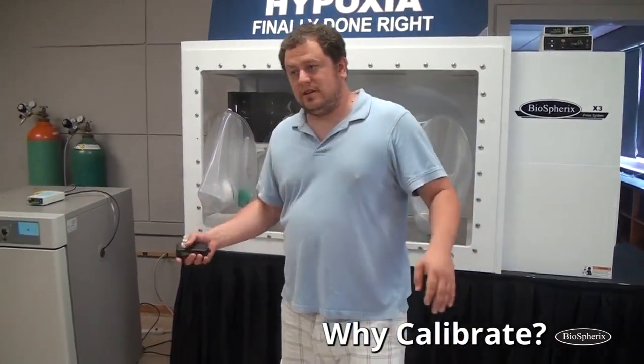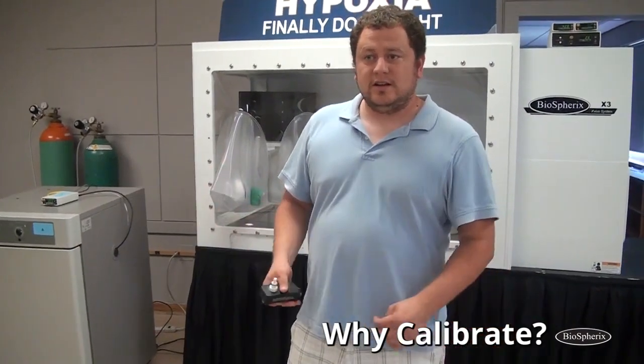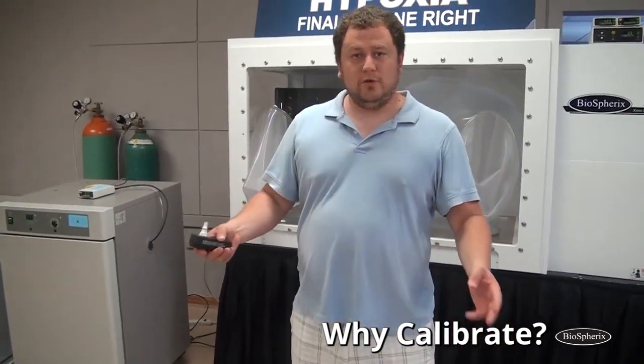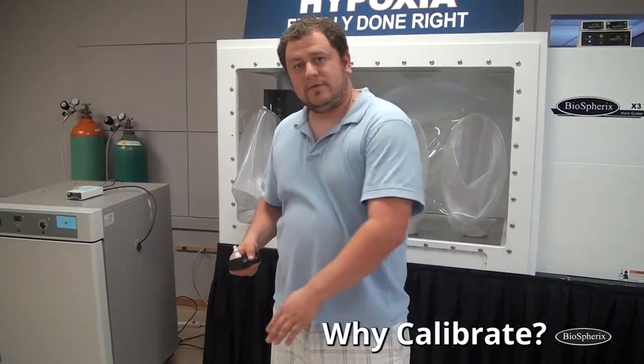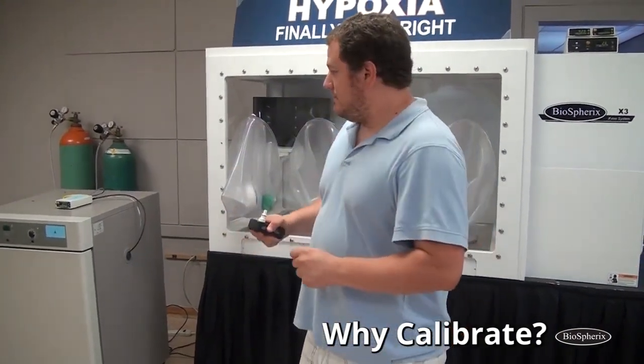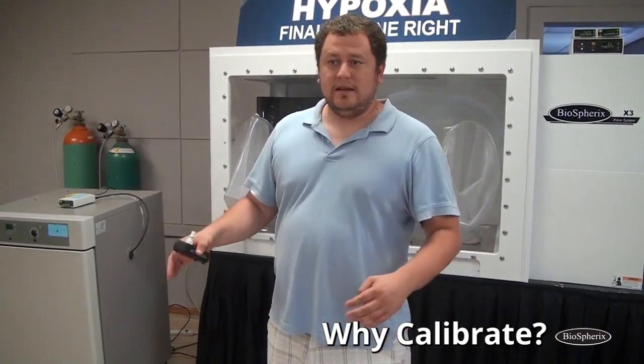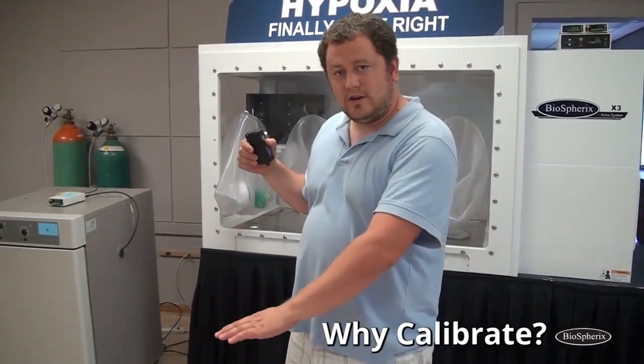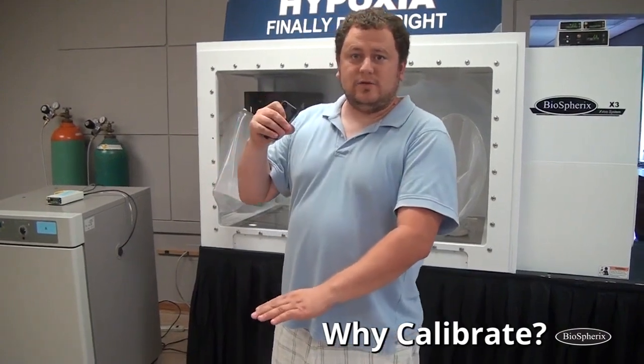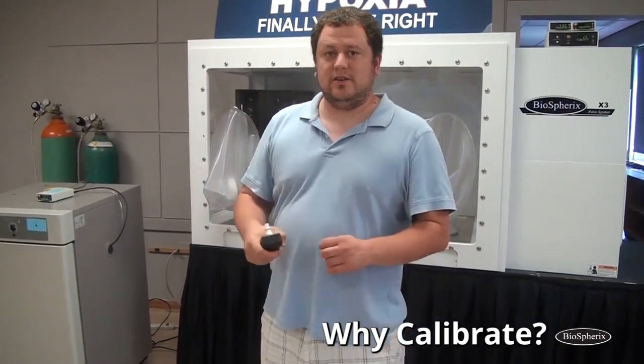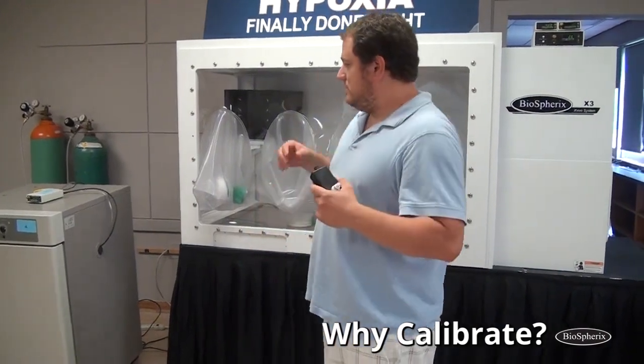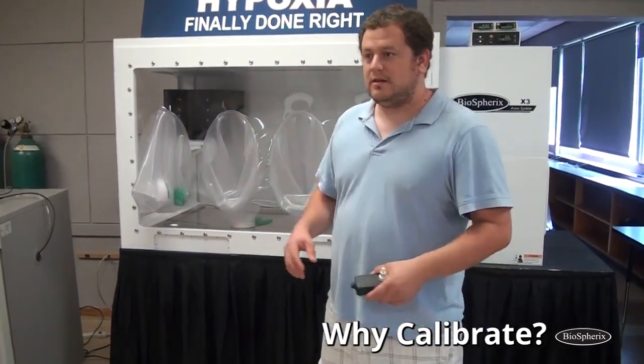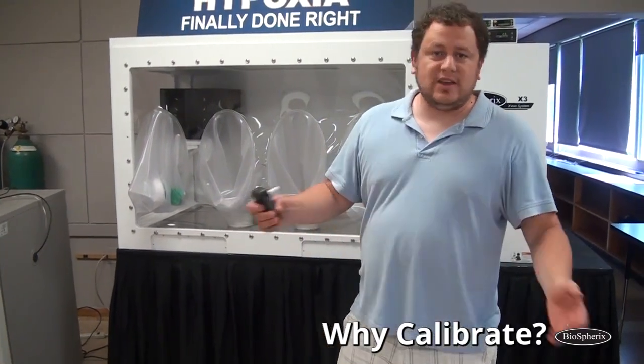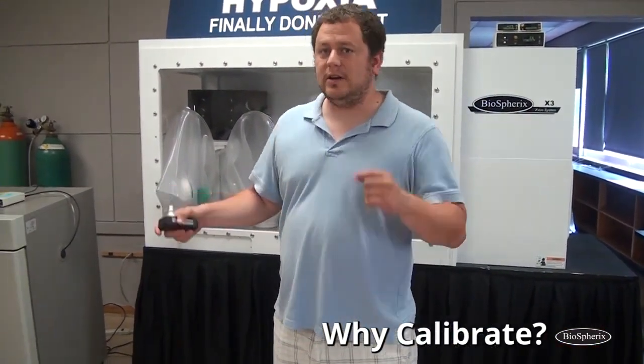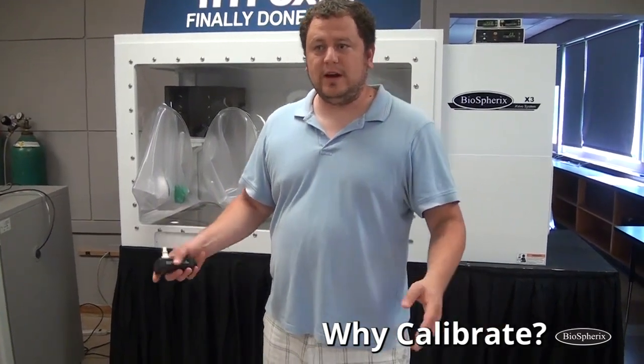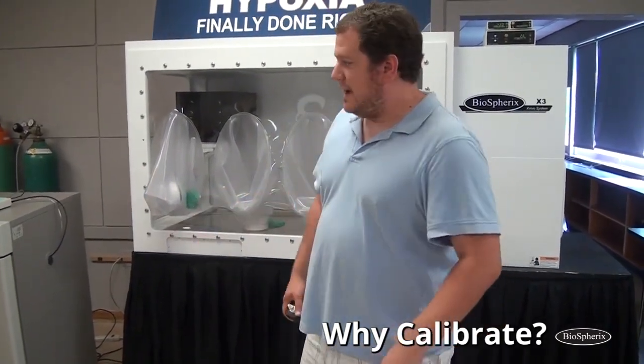So these sensors, the reading output is linear. So we tell our customers to do a 2-point calibration, a low point and a high point. And you always want to do a 2-point. And the idea is if you do a low at a known standard and you do a high at a known standard, everything in between is going to be accurate. So once a month, it's a good idea to calibrate it. If you're not using it and it's just going to sit dormant for a few months, you don't have to calibrate in between. Just calibrate before you start the next time.